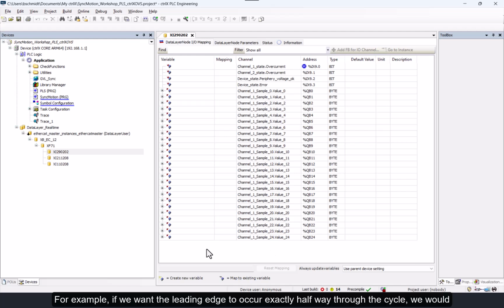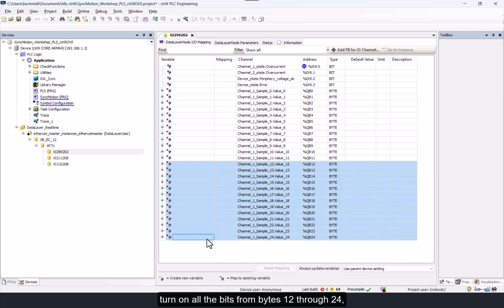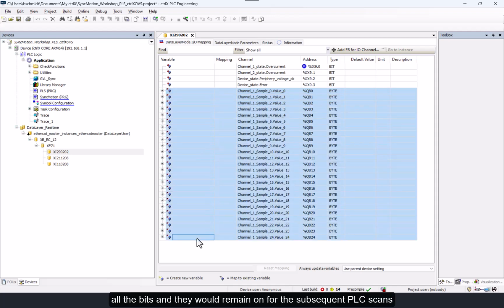For example, if we want the leading edge to occur exactly halfway through the cycle, we would turn on all the bits from bytes 12 through 24, while the bits in bytes 0 to 11 would remain off. This would be for exactly one PLC scan. Then in the next scan, we would turn on all of the bits, and they would remain on for the subsequent PLC scans until we want to turn the output off.